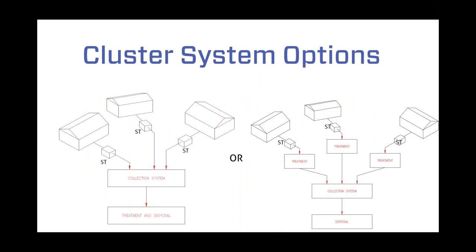Cluster system options — typically we see two different options available. The three houses on the left: pretreatment is done at each home, so each home on each lot will have a septic tank for pretreatment. This partially treated effluent then will flow to a community collection system, and from there it'll flow to a community treatment and final dispersal system. So in this case, only pretreatment is done on each lot.